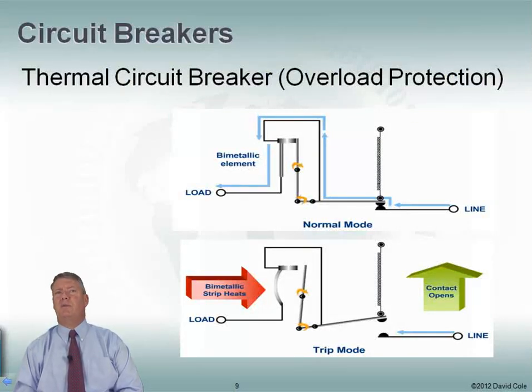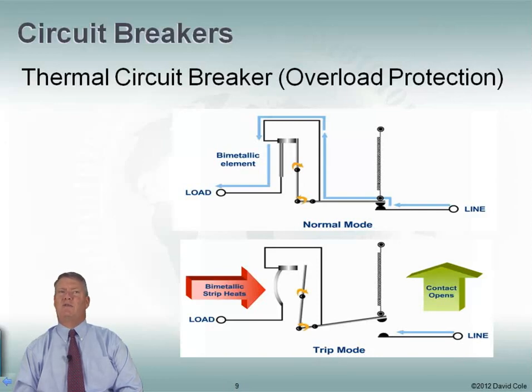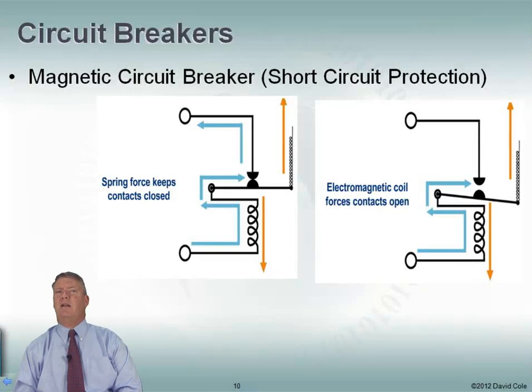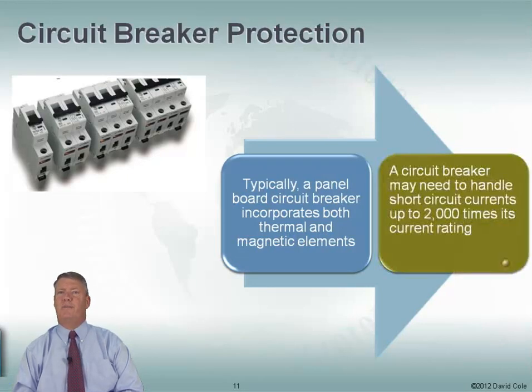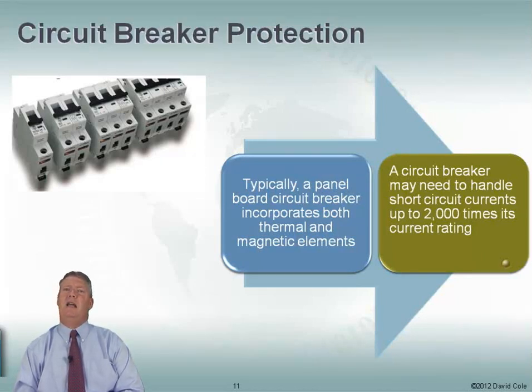There are two types of circuit breakers. One is a thermal circuit breaker that protects against overloads — if I get an overload, it trips the breaker, opens up the circuit, and therefore no more power flows through. The second type is a magnetic circuit breaker, which protects against short circuits. The nice thing is a typical panelboard circuit breaker has both thermal and magnetic elements, so it protects against both overloads and short circuits. A circuit breaker may need to handle short circuit currents up to 2,000 times its current rating.